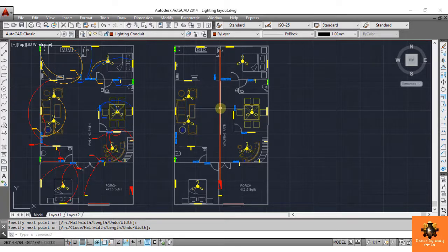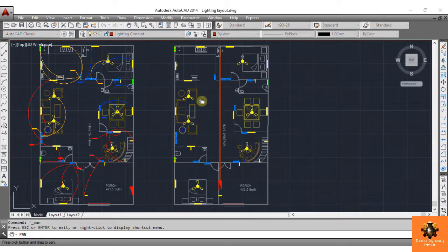Okay. Now take the sub branches from this branch for all the rooms. But remember one point here: as a professional engineer you have to take branches absolutely vertical or absolutely horizontal with respect to this main branch. If you are taking the sub branch horizontally from here, then this sub branch conduit should be at 90 degrees with respect to this. Or if you are taking it vertically, then that conduit should be at 0 degrees with respect to this. As a professional engineer you should not go with diagonal branches.